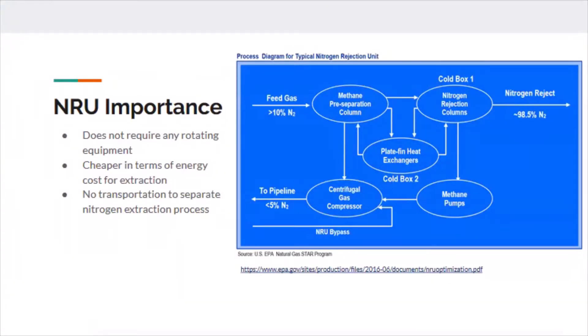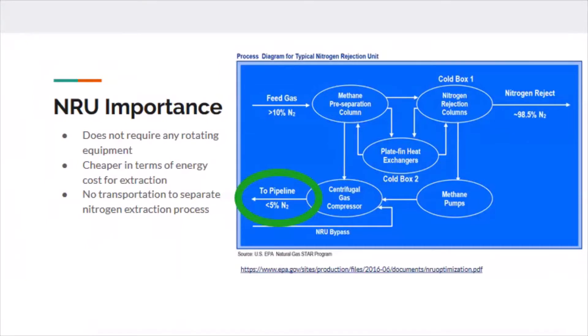After going through some other separation processes, it's important to see the LNG stream coming out with less than 5% nitrogen. Before NRUs were in place, this concentration could be upwards of 50% nitrogen inside that stream.